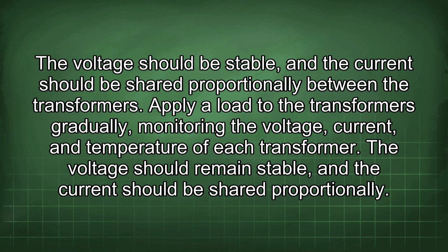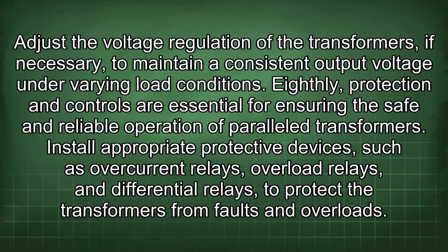Apply a load to the transformers gradually, monitoring the voltage, current, and temperature of each transformer. The voltage should remain stable, and the current should be shared proportionally. Adjust the voltage regulation of the transformers, if necessary, to maintain a consistent output voltage under varying load conditions.